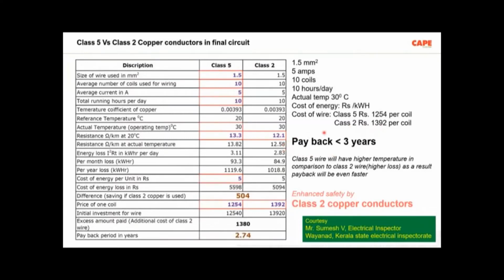Then with our calculation, we have established that the payback period is less than 3 years. So that means in an installation, if you buy class 2 conductor, of course you will be paying a little bit more, but your payback is within 3 years. Now this is actually a moderate calculation, but in a practical case, the payback will be even faster.